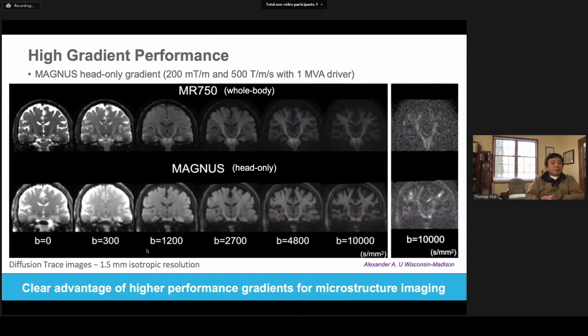This is an example from Andy Alexander from UW-Madison showing a comparison between the Magnus system and a whole body system. And here you can see that at different B values on these trace images, you can appreciate the higher SNR at higher B values as a result of the shorter TE. So here's one of the B10,000 direction images showing the major difference between a whole body system and a specialized head-only system like Magnus.